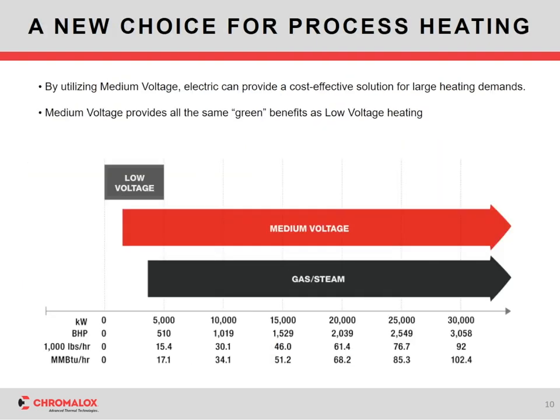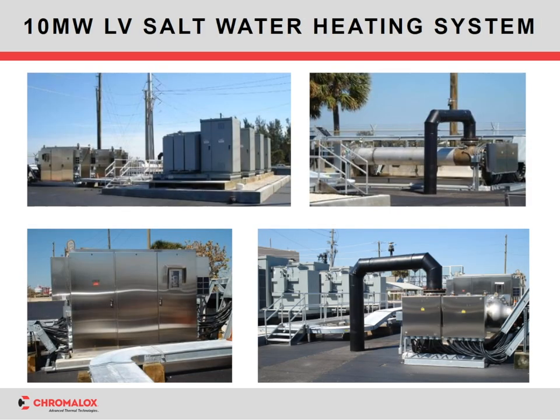And that's really what makes medium voltage such an exciting new opportunity for an efficient heater design. If we look at how the profile was in the past, there was a pretty clear split between low voltage and gas and steam usage. Now medium voltage crosses not only some of those intertwining applications from a kilowatt standpoint, but it stretches even further up into a practical design for large heating applications.